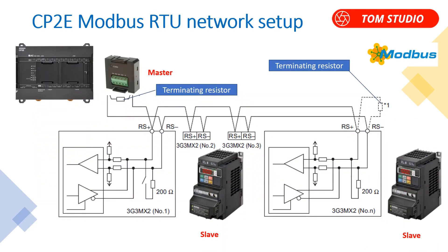CP2e Modbus RTU communications setup. CP1L and CP2e both support the simple Modbus RTU master function. In this example, we utilize this function to implement Modbus RTU communications from the PLC to 3G3 MX2 VSDs. The PLC takes the master role, with the MX2 VSD as the slave device. We use the CP1W CIF11 option board on the PLC and RS485 two-wire to link slave devices together.